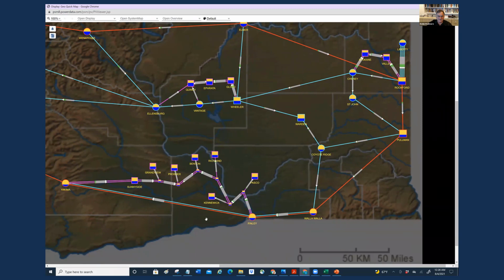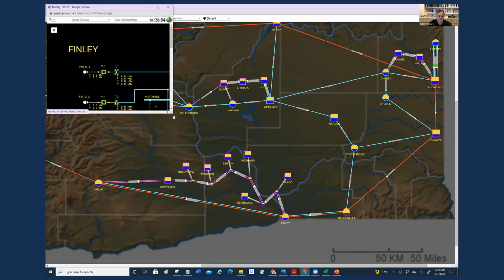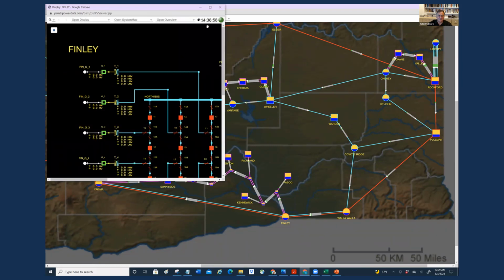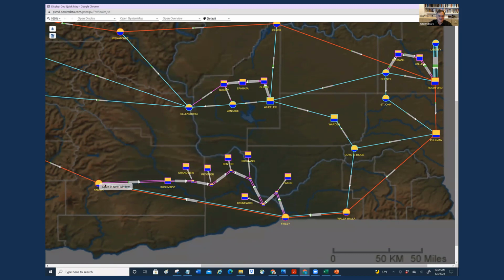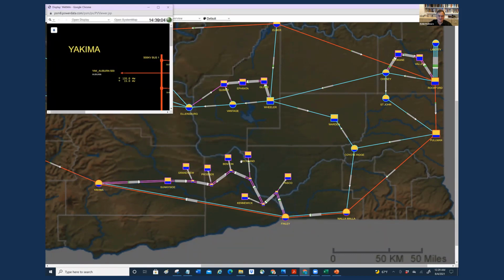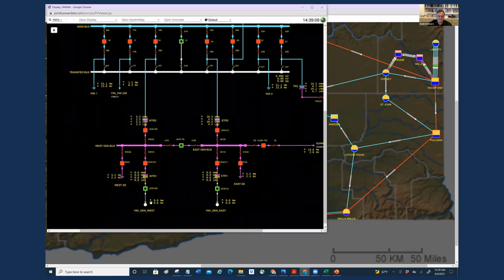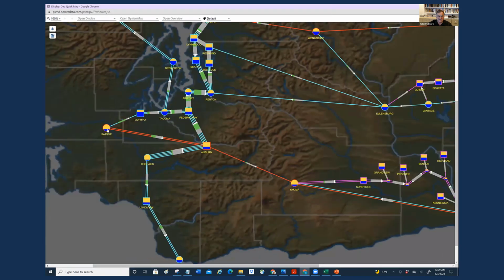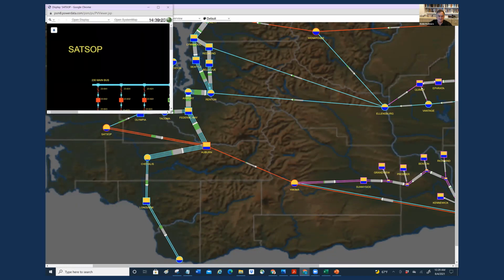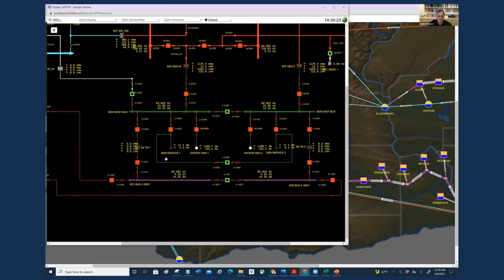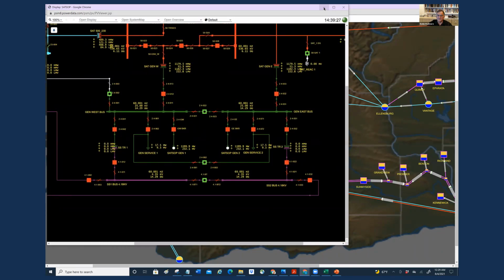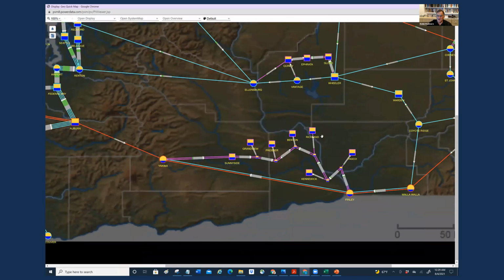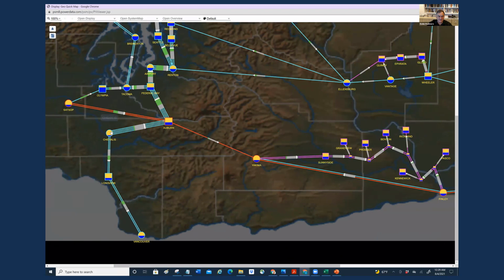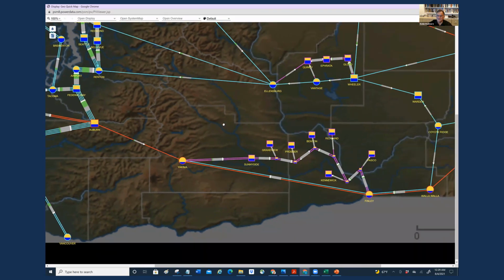But all these units are off. Take a look. We have some combustion turbines at Finley, but they are all offline. The breakers are open. We have 2 large solar units, power plants of 250 megawatts each at Yakima, but they're offline. The breakers are open. So we're coming all the way over to Satsop, where we have 2 very large nuclear units of 1,200 megawatts each. And so those will provide the support for reactive switching at Walla Walla. We'll get some support from down at this large coal plant at Chehalis, but really, to get a good approximation, we'll just consider those 2 sources.